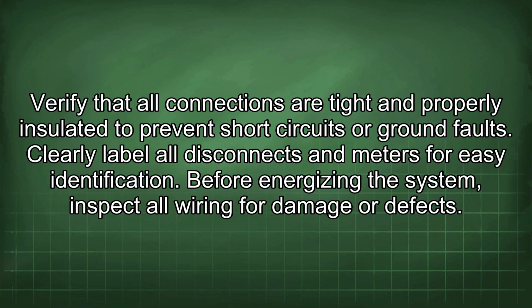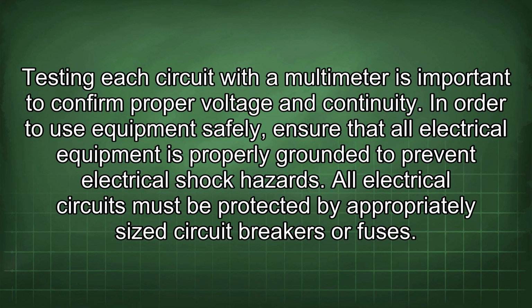Clearly label all disconnects and meters for easy identification. Before energizing the system, inspect all wiring for damage or defects. Testing each circuit with a multimeter is important to confirm proper voltage and continuity. In order to use equipment safely, ensure that all electrical equipment is properly grounded to prevent electrical shock hazards. All electrical circuits must be protected by appropriately sized circuit breakers or fuses.